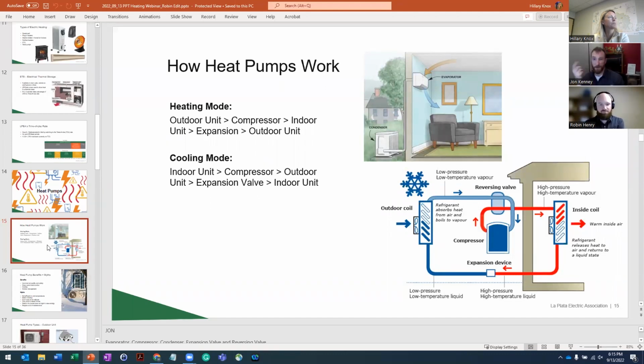Typically a 410 refrigerant flows through each unit. At the outdoor unit there's a big coil system with a bunch of really fine fins, and outdoor air is pushed through there by a fan. All the heat is taken out of the air—we can do this even in the middle of winter down to -25, -30 degrees. There's still little bits of heat in the air that we can capture, pass into that coil assembly, and that heat gets into our refrigerant.